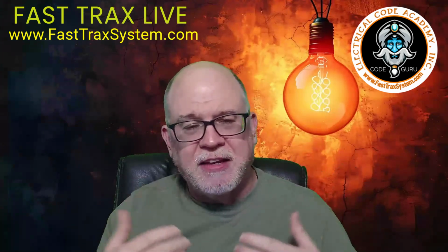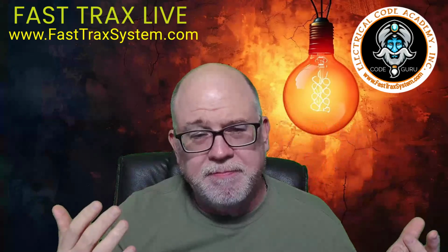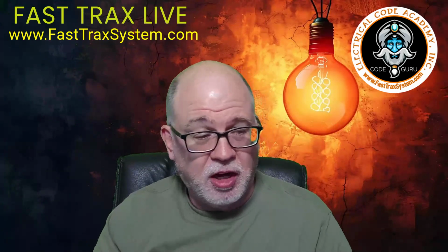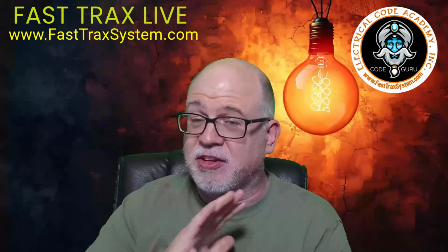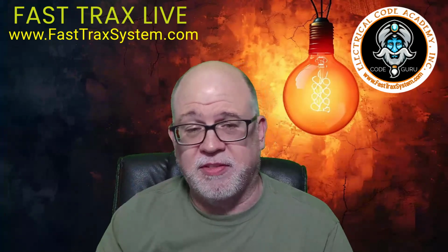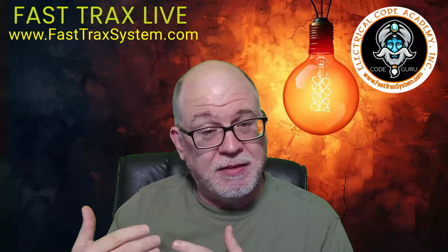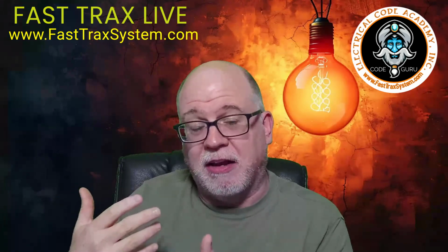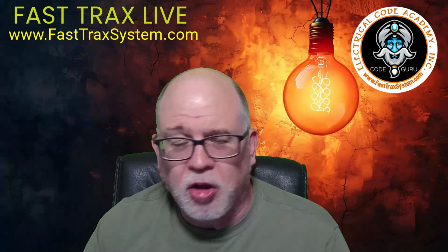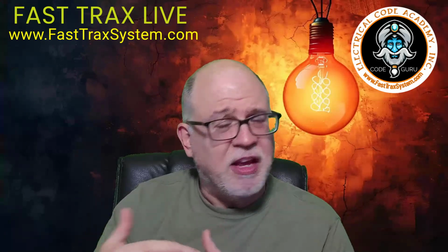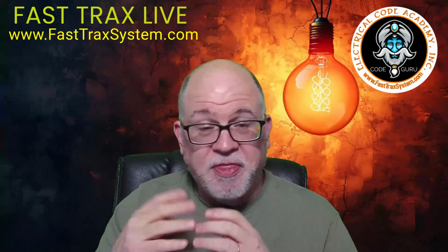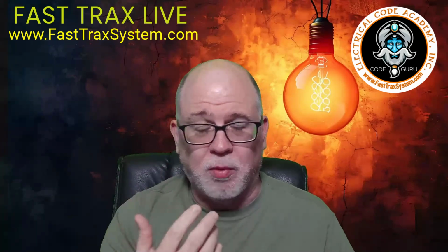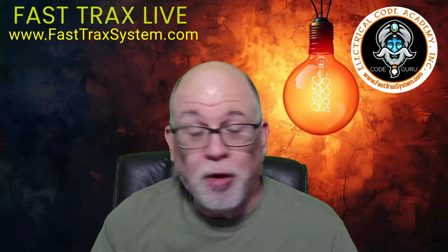So these are things that you should just lock in your memory. Learn that 6-12-foot rule, understand what a break in the floor line is, and understand when something is not considered a break and is considered wall space, like the fixed portion of a sliding door, or a railing that is fixed in place. That would be wall space, and so it's going to require you to figure out how to put a receptacle in there. Also, remember that receptacles inside of cabinets, higher than 5.5 feet, or built into equipment are not going to take the place of your normal spacing requirements. Hopefully you got something out of that.